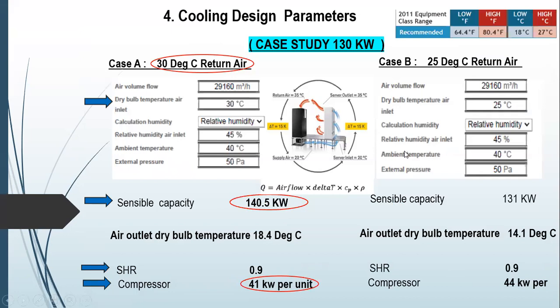To give you a case study, what happens? Let's say the temperature is maintained from 18 to 27 at the rack level. So what is the impact on the cooling unit? Most of the time the CCU units are designed at the return air temperature. So as I said, if the server room has to be maintained at 27, then the return air given to the PAC is also taken at 25 degrees. Thereby, keeping a delta T of 10, 11, the supply from the CCU is 14.